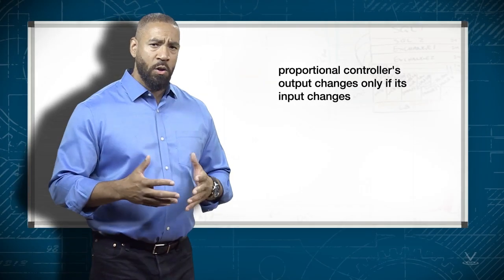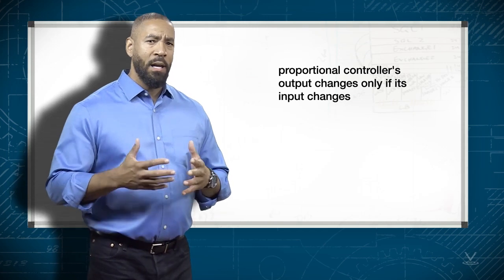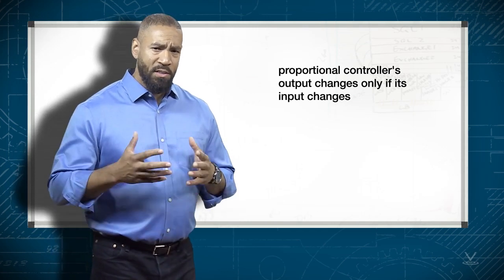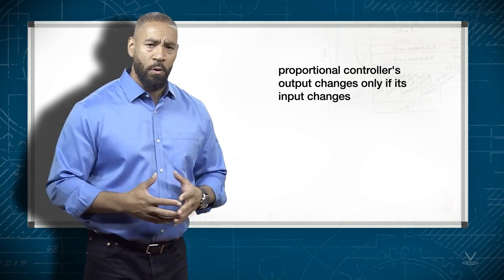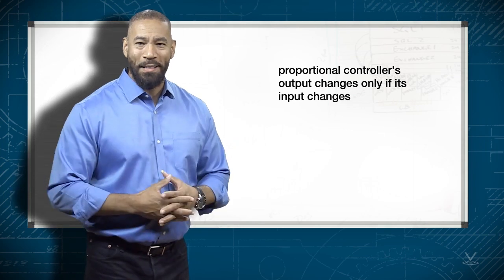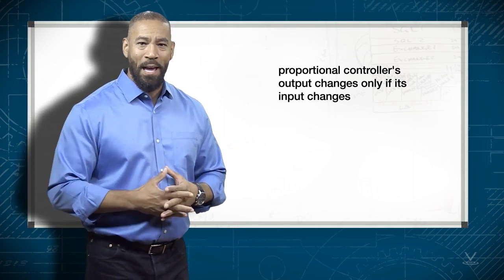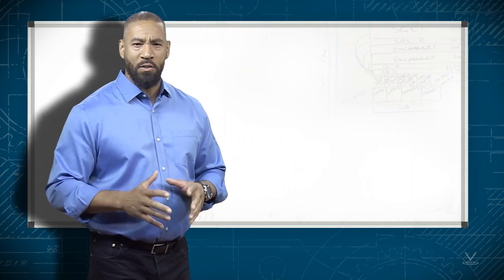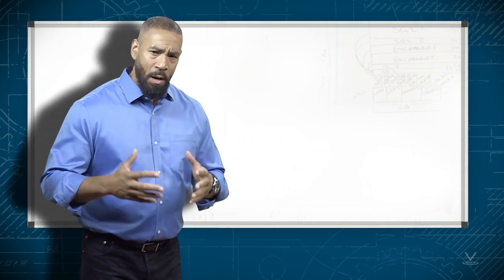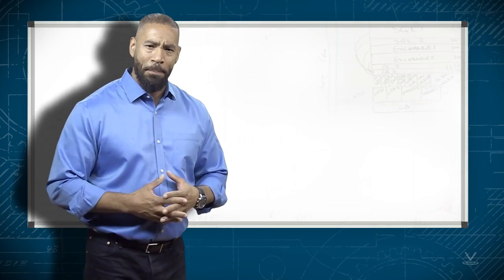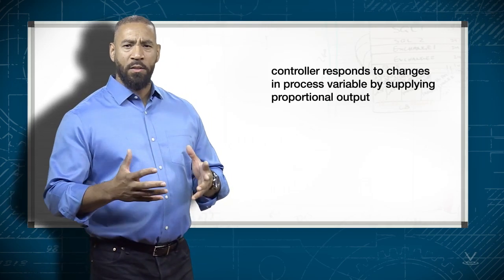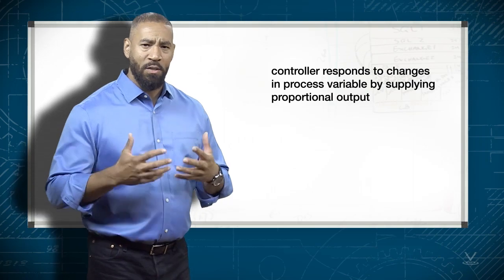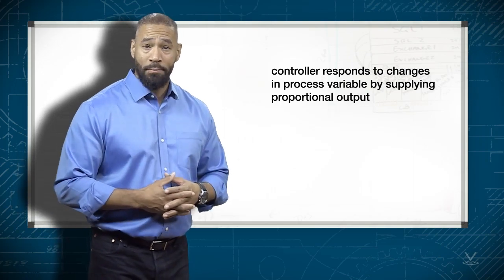A proportional controller's output changes only if its input changes. This is characteristic of all proportional controllers. We've just seen one simplified example of how a controller can be designed for proportional control. Other controllers may have different mechanisms and may balance themselves in different ways, but the result is always the same. The controller responds to changes in process variable by supplying a proportional output.